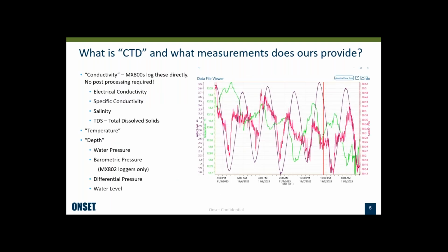So I think this slide is something that most of you are aware of. What is CTD? It stands for conductivity, temperature, and depth, and it's just a common way of referring to sensors that do this range of measurements. And there are actually several different forms of conductivity. You can have electrical conductivity, which is the direct measurement of the conductivity. Specific conductivity, which is the conductivity adjusted to 25 degrees Celsius. That normalizes for temperature variations.